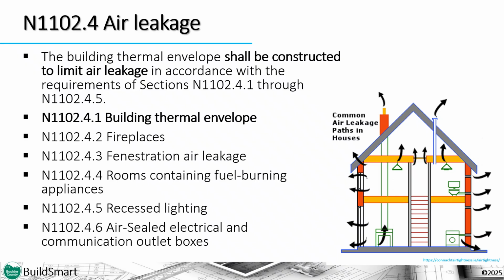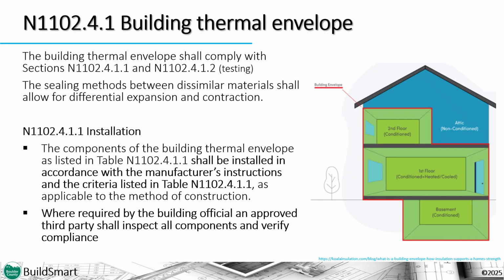The BuildSmart code uses the air barrier, air sealing, and insulation installation table to describe how the continuity of the building thermal envelope is constructed to achieve the air leakage requirements that are laid out in the blower door testing section that I will discuss in just a few minutes. These installation requirements are in addition to manufacturer instructions to better ensure performance.